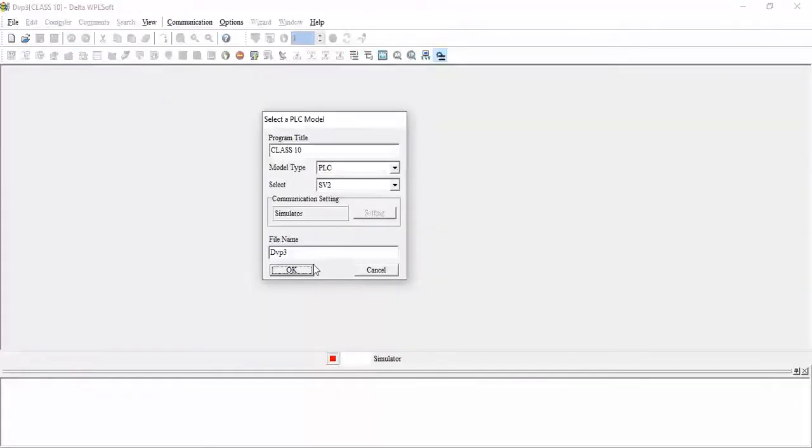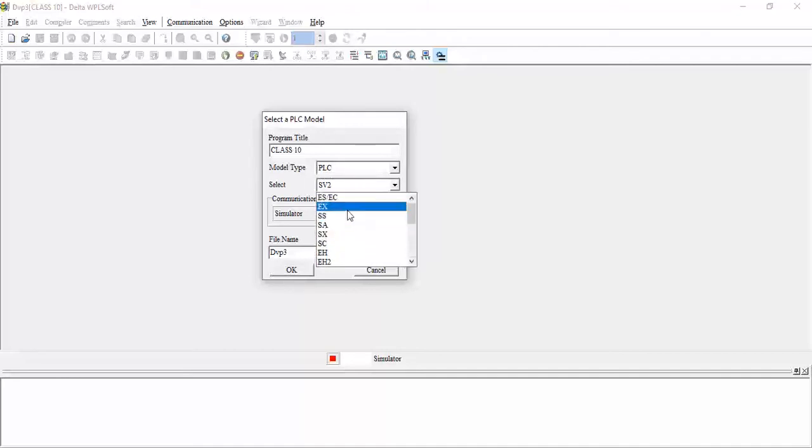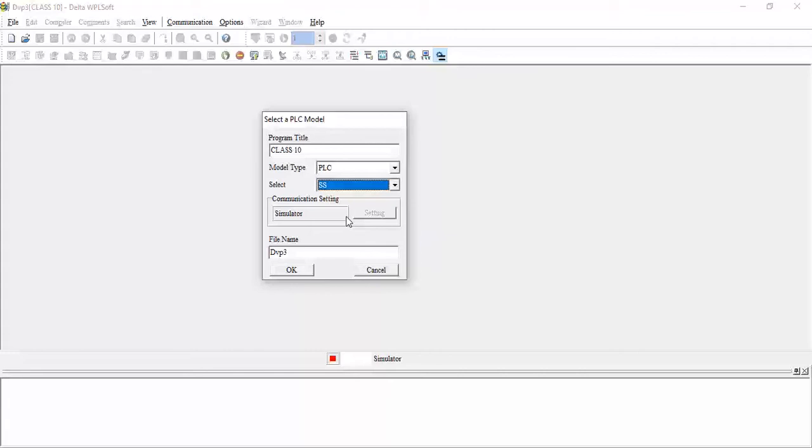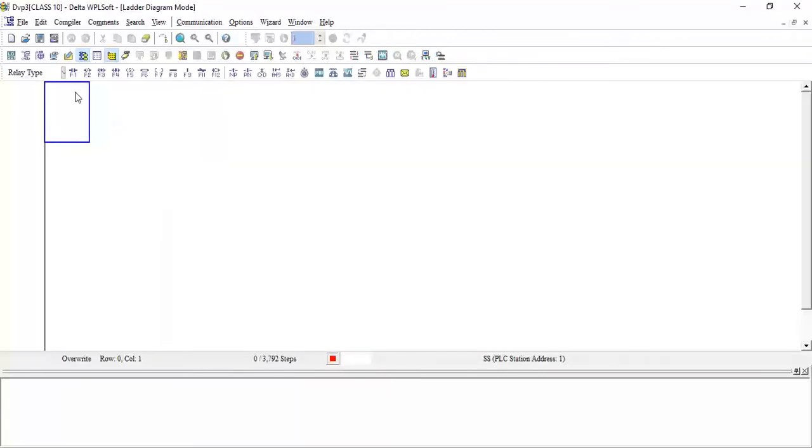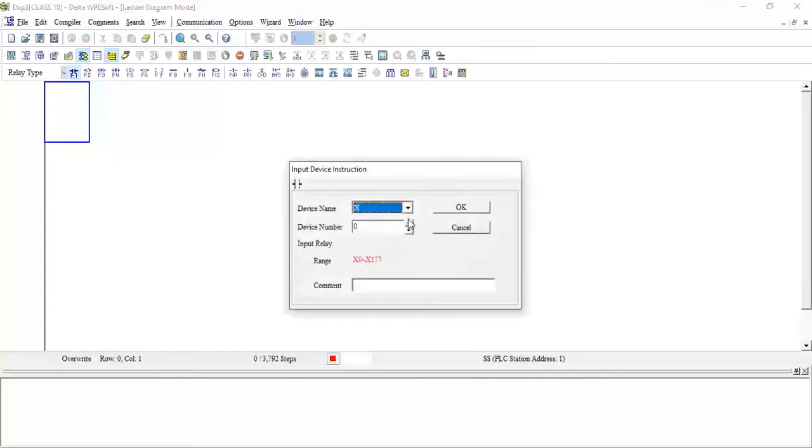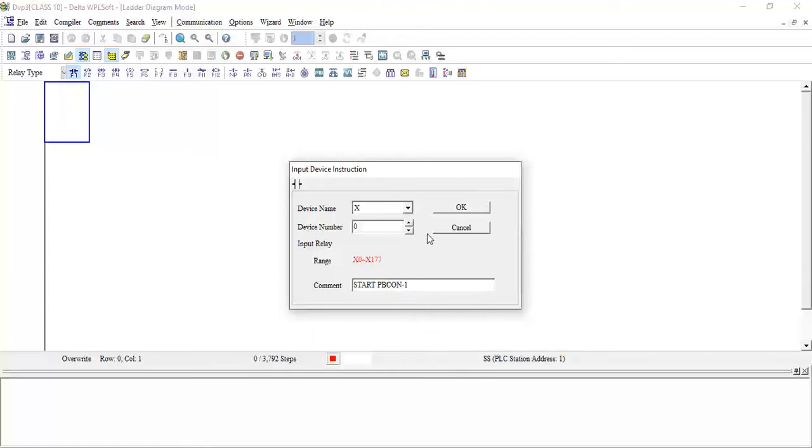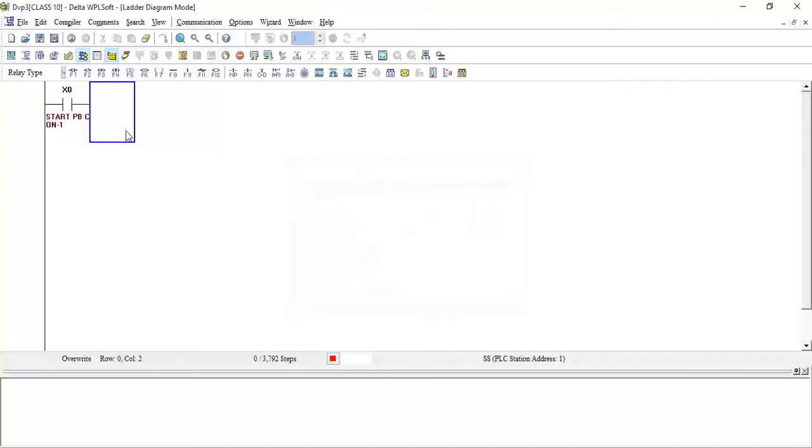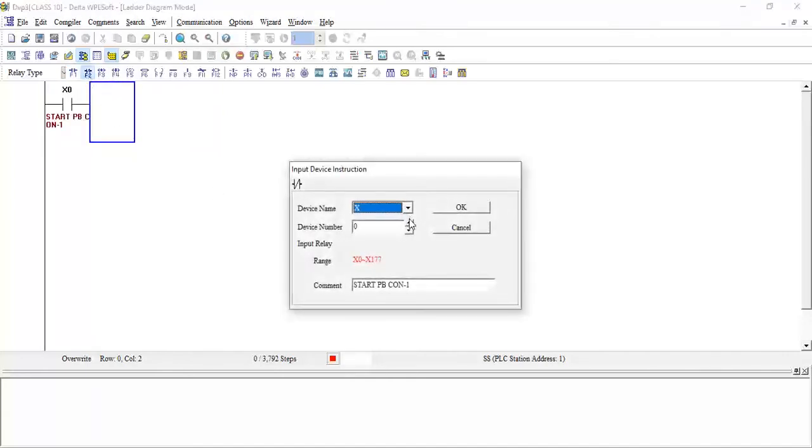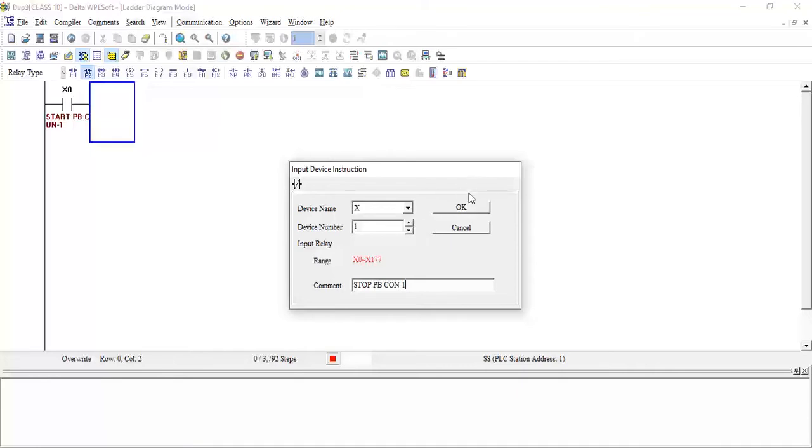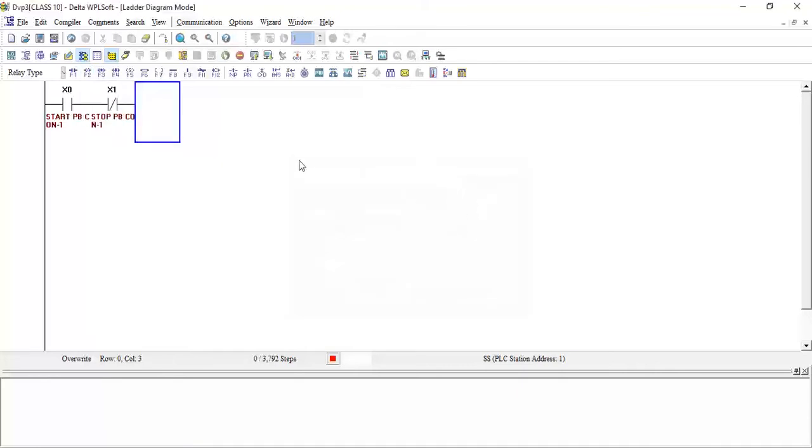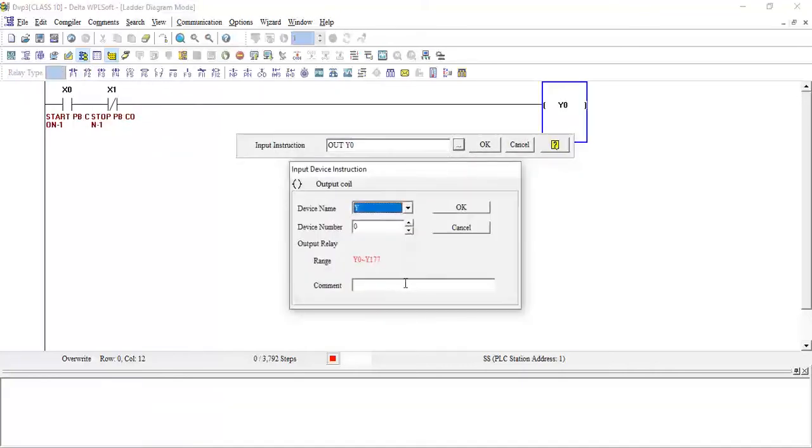We will take one new file, class 10 PLC. This is the ladder logic. So initially we need to turn on our conveyor 1. We will take the start push button manually operated, write here start conveyor 1, click OK. Then we will take NC for the stop, stop push button conveyor 1, click OK. And I will write here output Y0.